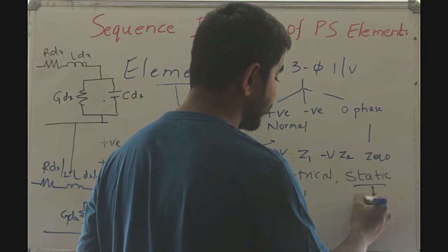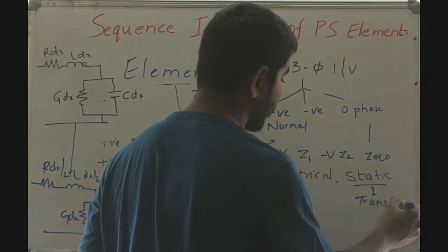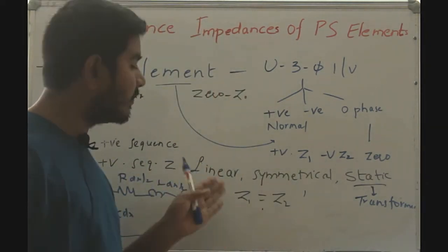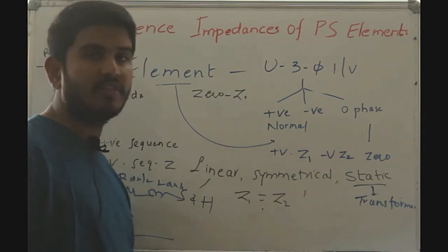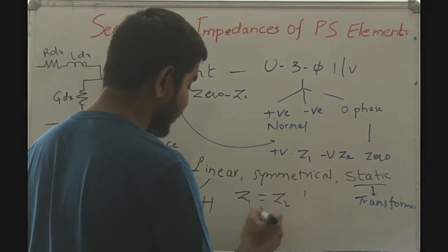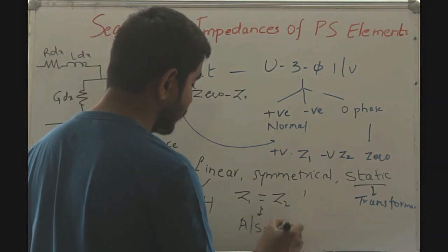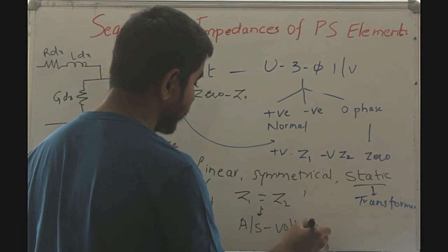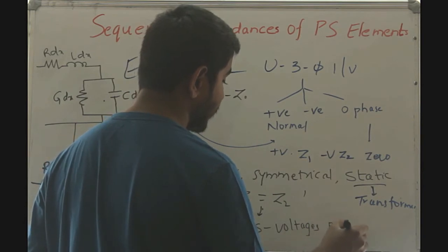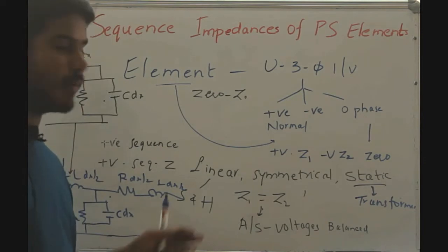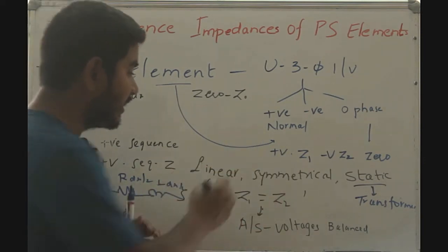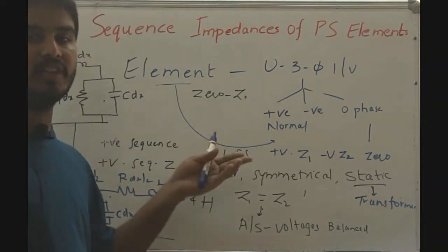For the static circuit — for example, a transformer, which does not have rotating parts — the positive sequence impedance will also equal the negative sequence impedance. For these circuits that are linear, symmetrical, and static, the positive sequence impedance equals the negative sequence impedance, provided the condition is that the applied or source voltages are balanced. When the source voltages remain balanced, the sequence impedances of these LSS circuits are independent of the phase order.